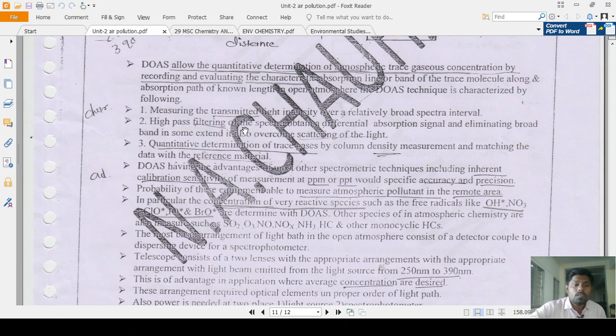Here a beam of transmitted light is used with a relatively broad spectral interval. When using the differential absorption signals, they eliminate the broad band and we get the sharp peak here. In quantitative determination, we can use density measurement techniques, which are matched with the reference material. DOAS has advantages over other spectrometric methods, including inherent calibration, sensitivity of measurement at the ppm or ppt level, with high accuracy and precision.